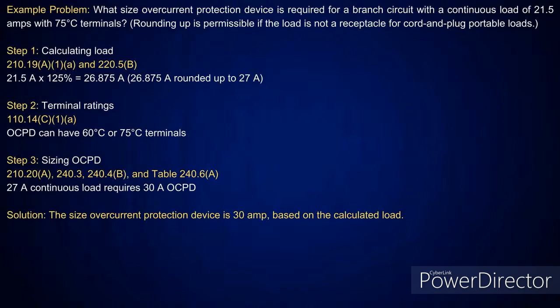All right. Now, this is going to get us into overcurrent protection devices, and I'm going to give everybody a rule of thumb before we start this. And I'm going to prove this as we're going through all these calculations. Now, this is something I did on NEC Live. They had me on. They wanted me to do conductors and overcurrent protection devices, and they wanted me to mainly do calculations. And one of the statements I made is, if you size me at 125% or less, you're going to go up to the next standard size overcurrent device. Any percentage above that, you're going to drop down to the next standard size overcurrent device. You need to remember that little tip.